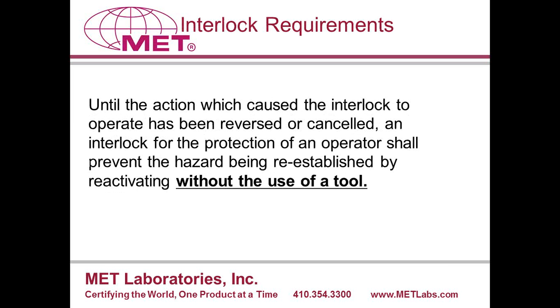There is a small change to the interlock standard which can be significant in terms of design. It requires that an interlock cannot be defeated without either removing the hazard or using a tool.